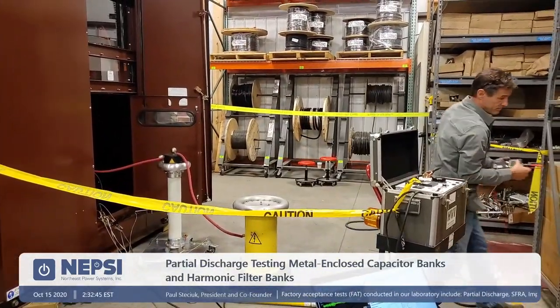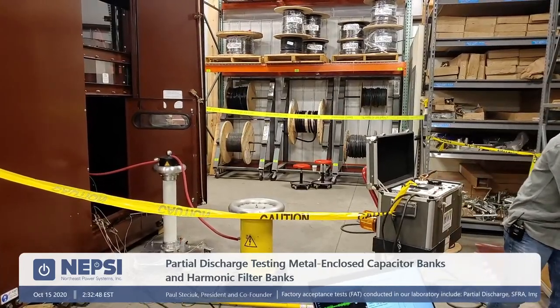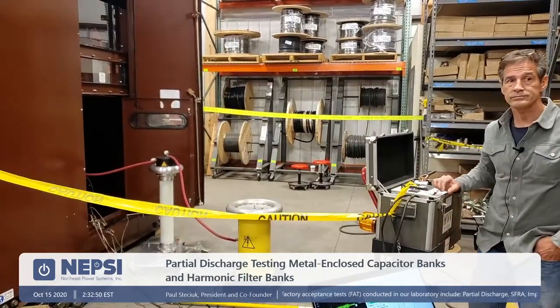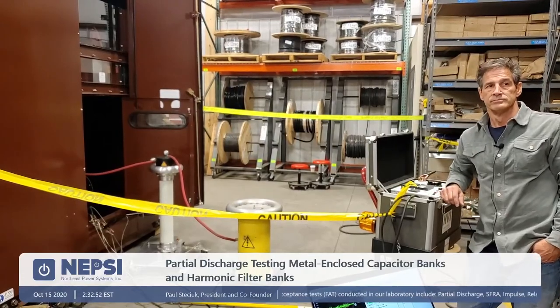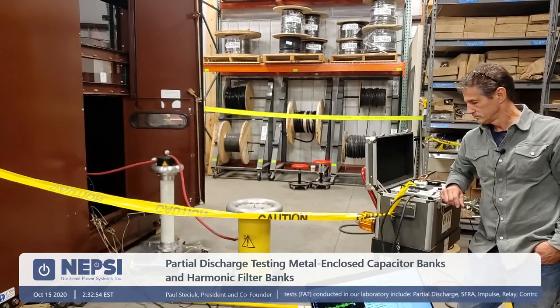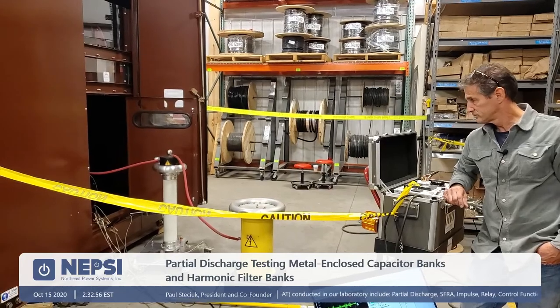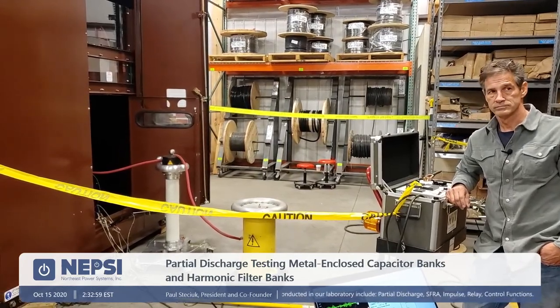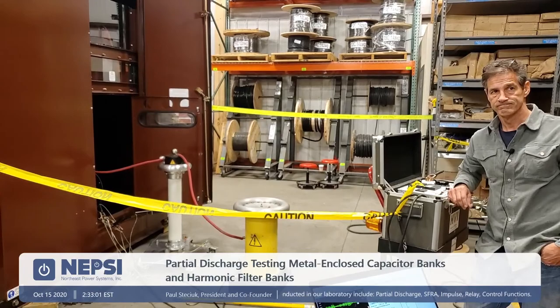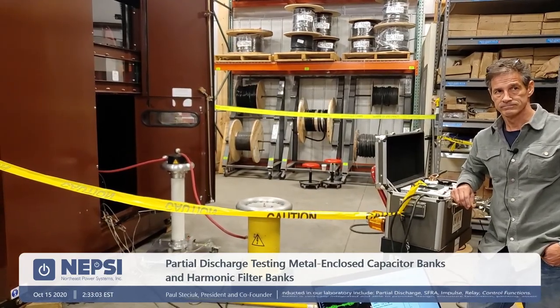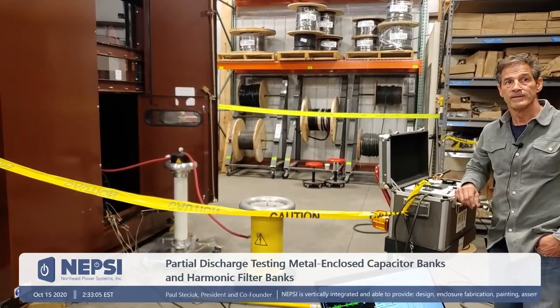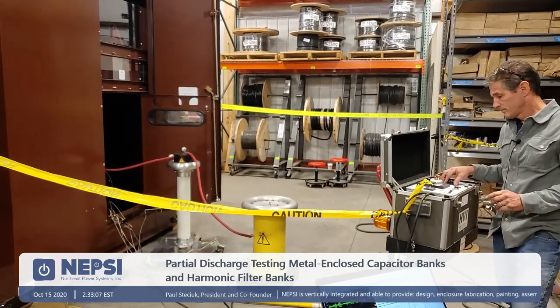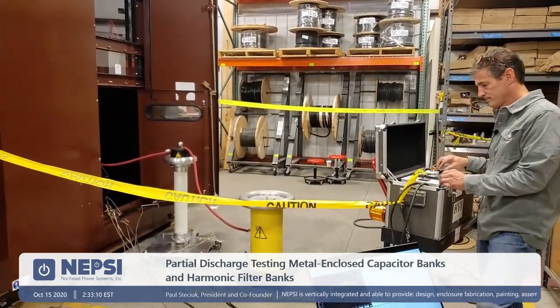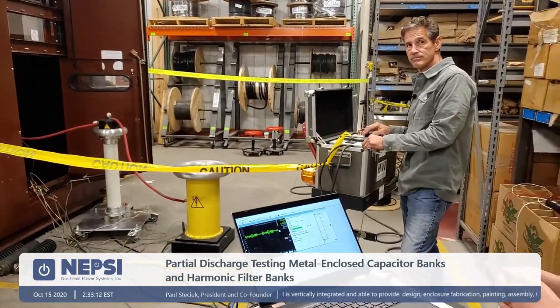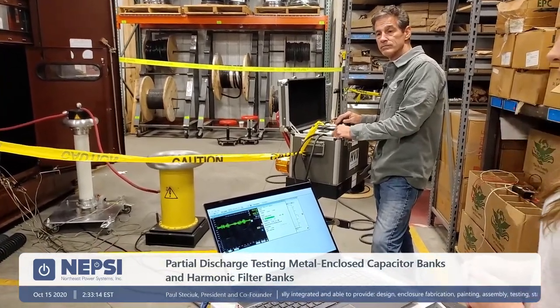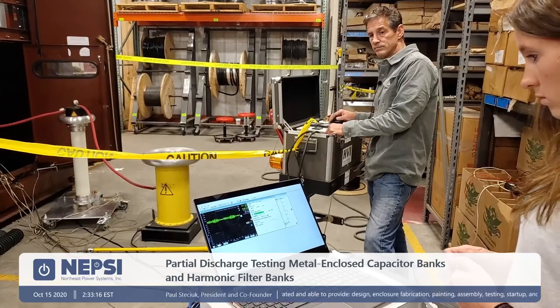So basically, this is a Haefely PD test set. It's a DDX 9121B partial discharge detector. We have the 9230 series capacitive voltage divider, and the calibrator that he was using there is a KAL 9511 calibrator. So now they're going to bring the voltage up to 10 kV, and basically that is to get the correct voltage ratio in the test instrument here. So when we're conducting the test, the device knows what voltage we're at.